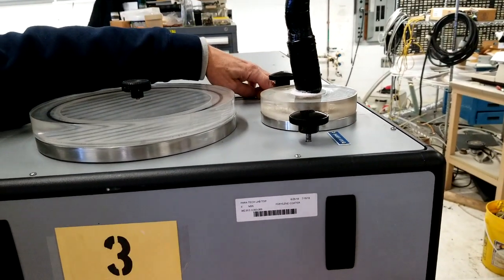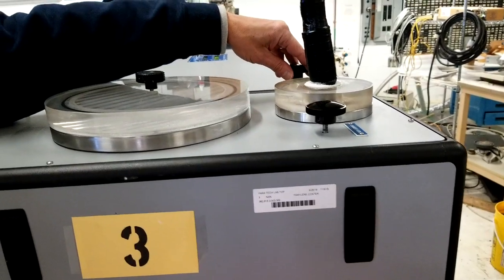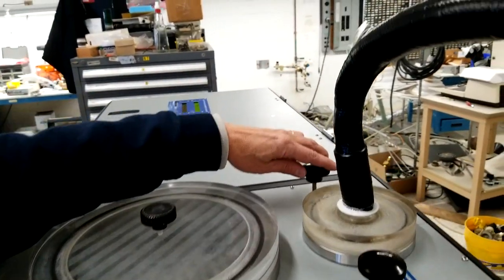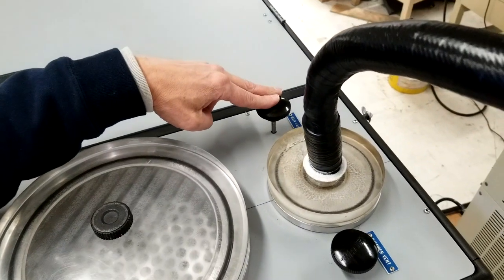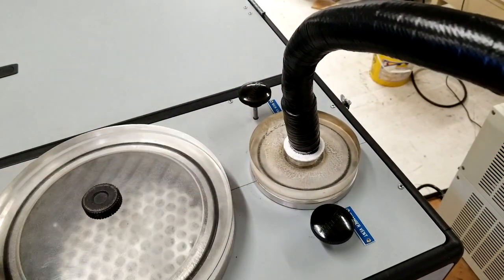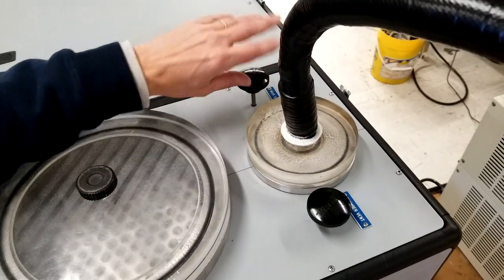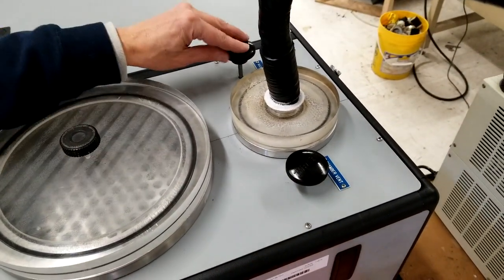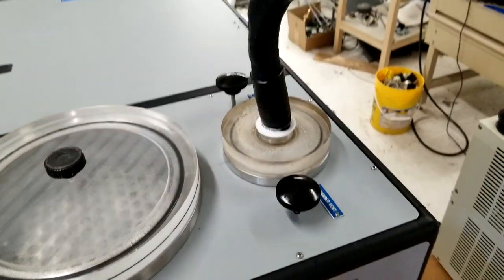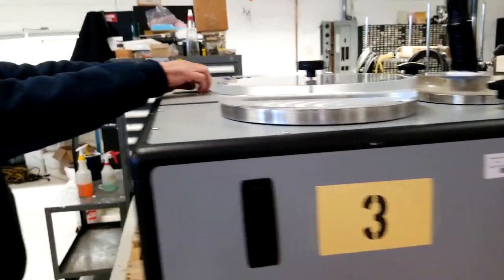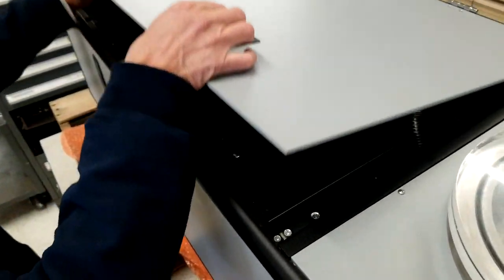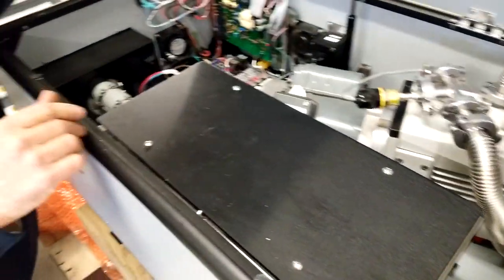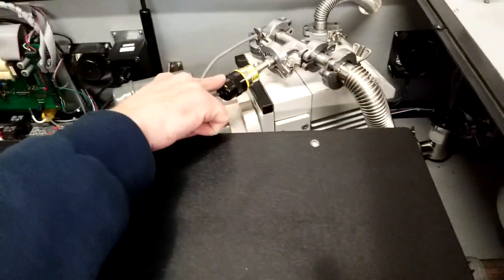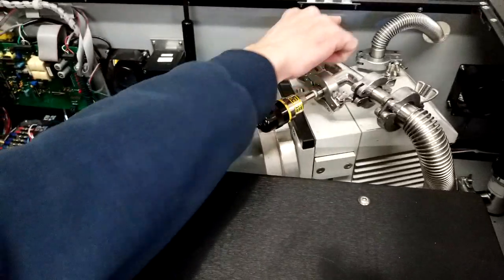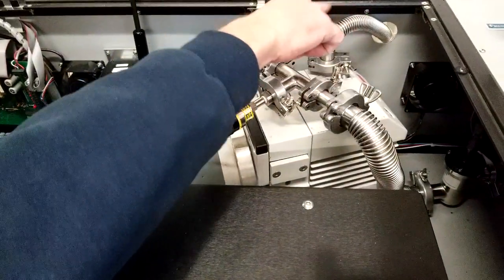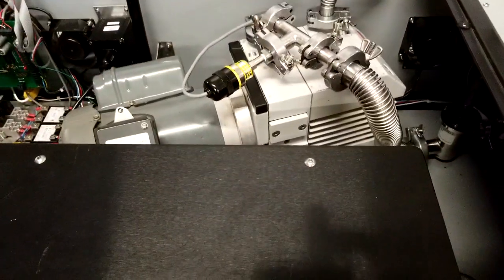The vacuum pump is controlled by using your main vacuum valve here, which is now open. And you can see it's cold here, so it's at minus 80 degrees. This is your evacuation valve. So this will evacuate your entire system. If you need to isolate it to vent it, you would then close this and then open your vent valve. Quickly looking inside here, I'll just point out a few things, and then we'll go ahead and run the program. Here's our vacuum pump with our vacuum gauge here, and it is being exhausted to the back. So that line you see in the back is your exhaust for your vacuum pump.